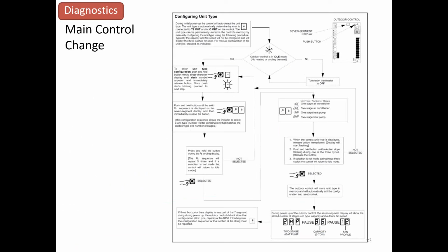If you do change the main control board, though, you have to reprogram it. It's more than likely going to capture the tonnage properly in the outdoor fan model, but that heat pump and AC, sometimes they don't necessarily recognize that. So you want to make sure that you're aware of that when you do a board change under warranty, that the technician runs through this.